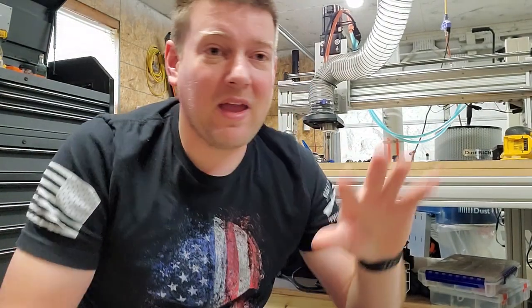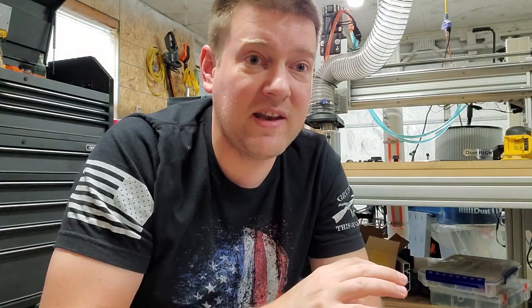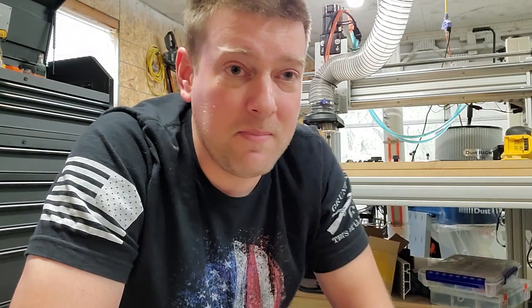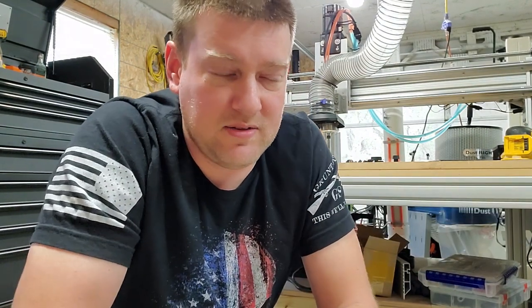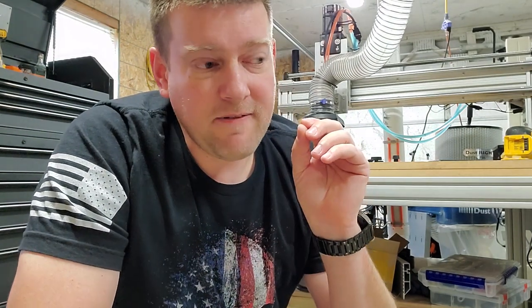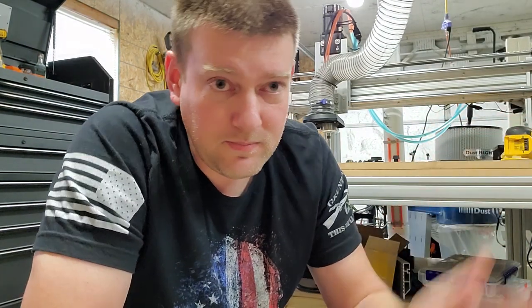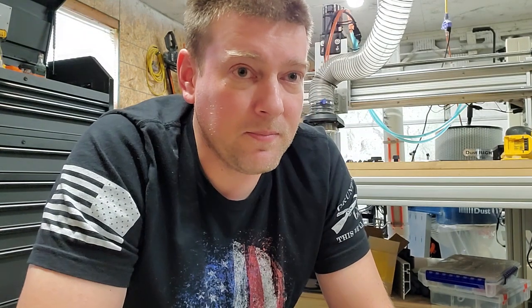FOBI acts as the middleman — the account manager and liaison between parties like dotmed and eBay — which makes my life way easier. I work for a major hospital; they're not too concerned with money, but we're here to decrease downtime and decrease costs, and I can do both. For the cost of shipping one HD Connect to Karl Storz for a flat rate repair, I can buy three HD Connects. One I can roll out immediately — just program in the hospital name and it's ready. The other two sit on a shelf for the next problem, which will probably be in a month.